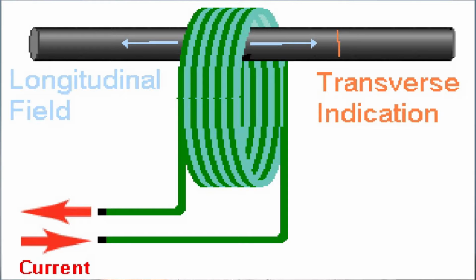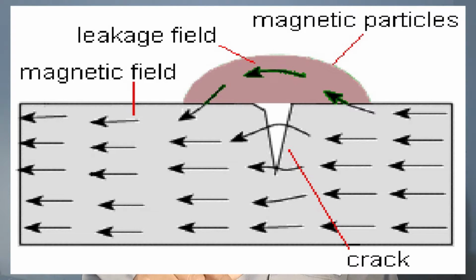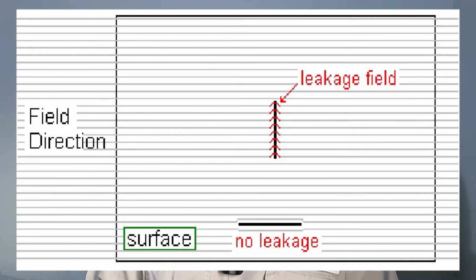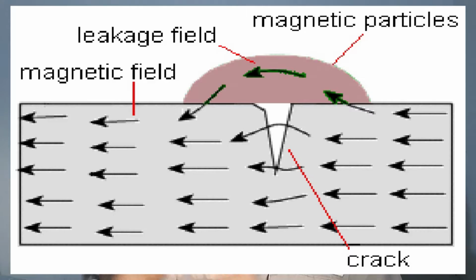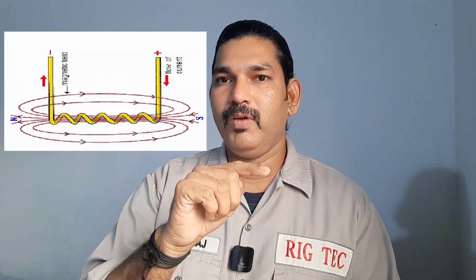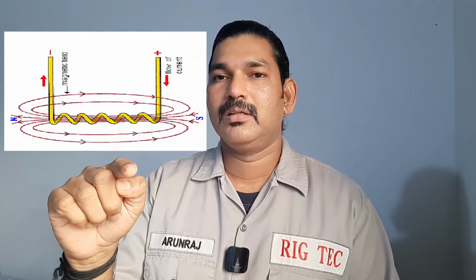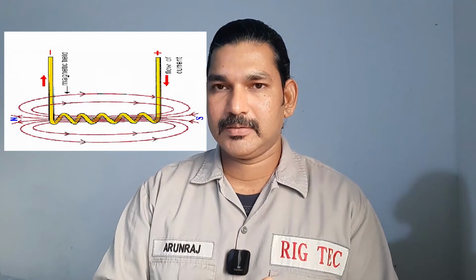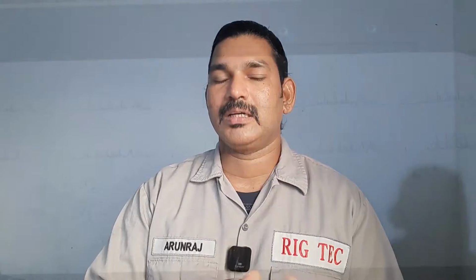How are the shoes generating electronic pulses or signals? If there is any surface discontinuity, the magnetic flux will come out from the discontinuity, so there is a magnetic field. If the magnetic flux comes out from the tubular body or calibration pipe, any tubular product, there is a magnetic field. The shoes are a coil. Any conductor will cut the magnetic flux. The conductor will produce a small amount of electricity. That electricity is sent to the console. The console will amplify and convert it to a graph. These are the main things happening in the console.